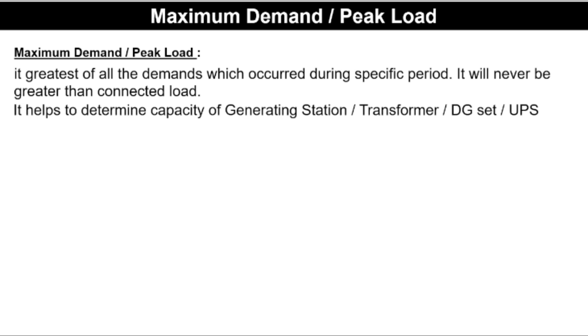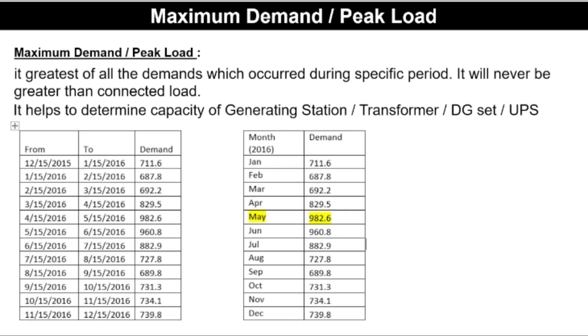Suppose this is the operating load of a particular system during January 2016 to December 2016. During the period, the load is varying. In January the load is 711.6 kW, in February it is 687.8 kW, and in March it is 692.2 kW. You can see that the load varies continuously from January to December. The peak load or maximum demand of the system is 982.6 kW.